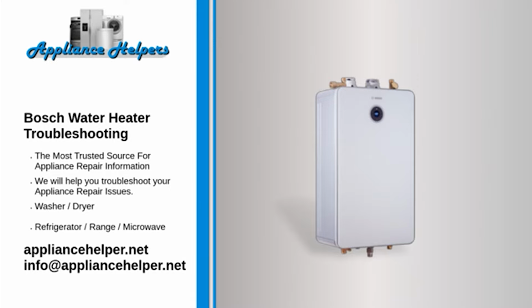Check the inlet gas particle screen for blockage. This can be done by looking at the gas inlet connection located at the bottom of the heater. Make sure that the gas pressure follows what was specified in the manual. If you need a reading, you have to call your original installer or a local certified gas technician to do so. Check for a plumbing crossover.